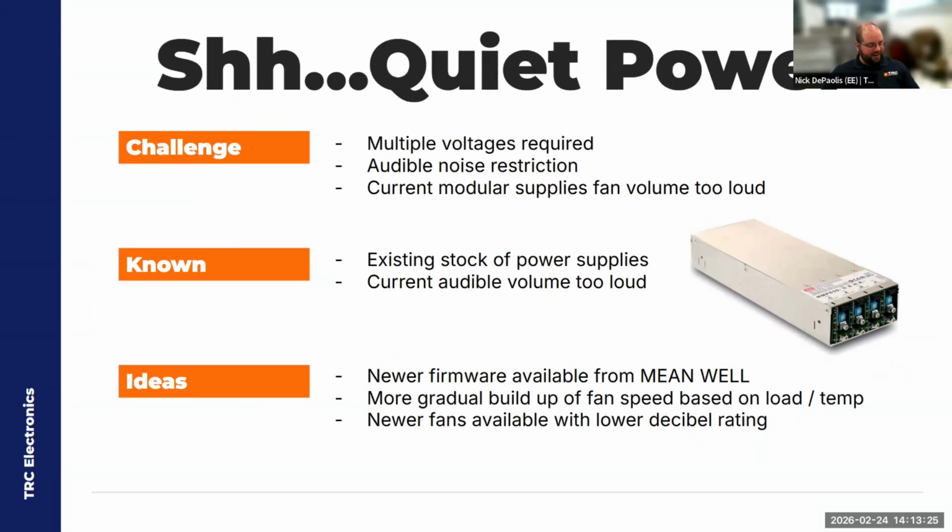Yeah, so essentially, a lot of clients, you'll see this come up from time to time, where anything that's fan cooled just inherently makes noise. And depending on the application, that could be okay if it's sitting in a closet somewhere. But if it's going to be anywhere where people are hanging around, it's going to get annoying really quick. So essentially, the client came to us, they were experiencing excessive audible noise issues from their fielded power supplies. The requirements they had basically were to provide multiple output voltages within a single chassis. They just wanted it quieter.